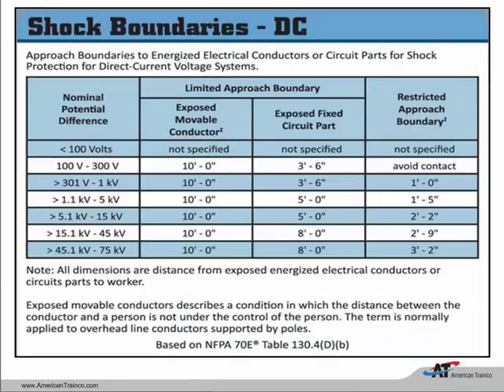And here's the one for DC. Very similar, except under DC they did have their label go all the way up to 300 volts for DC, with the restricted approach boundary saying avoid contact. So pretty much no restricted approach boundary there, just don't touch it up to that level. And then the restricted approach kicks in when they get above 301 volts for DC.